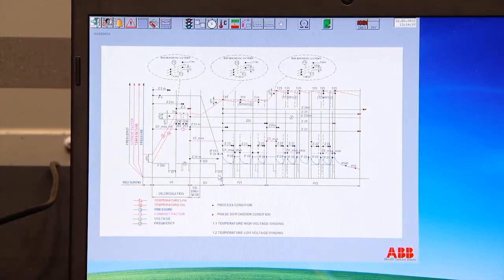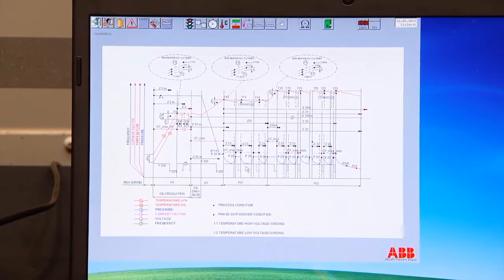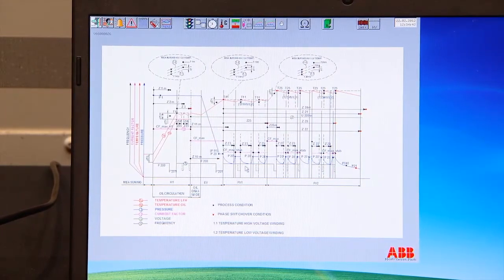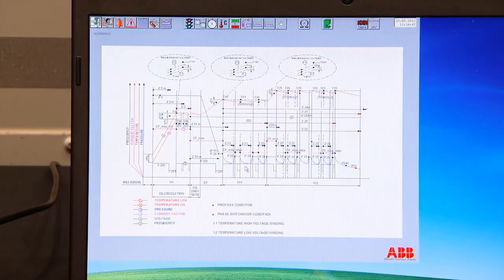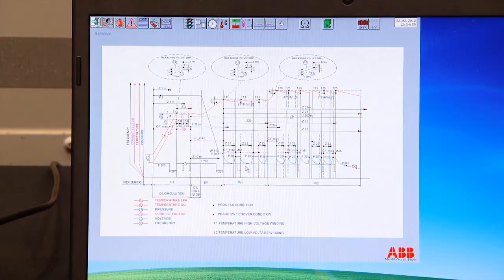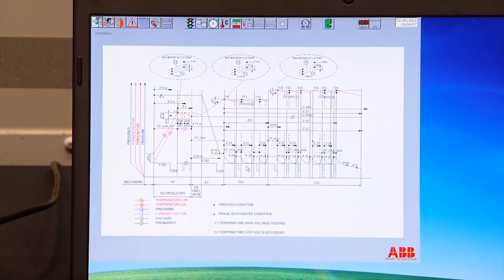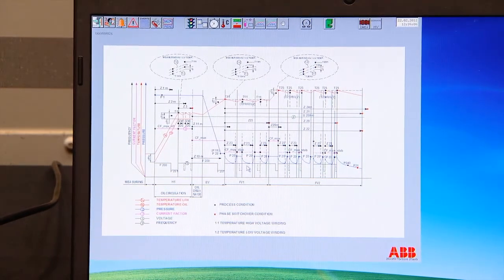That's reasonable, yep. Stabilize it for a couple hours, reheat for 2 hours to 90 degrees. No, you heat up to your 90 degrees. When you're reaching 90 degrees, then you wait 2 hours, and then you reheat again, because then you drop the temperature down to maybe 85 degrees, waiting another 2 hours, and reheating again after 2 hours has elapsed. That's automatically done. You set a parameter for that.